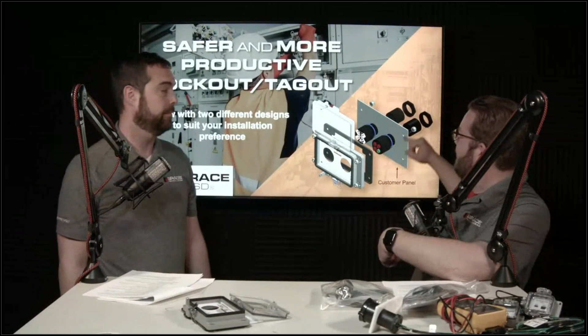You can see it back here - if you have an existing voltage indicator, you just mount the same thing, it goes right around it, and extends that platform out. A lot of OEMs include our R3W voltage indicator, so if you buy an OEM piece of equipment and want to add the ability to test for absence of voltage, this is an option. Likewise, if you just want to remove the R3W voltage indicator, the new check volt fits in the same size hole, so you don't have to worry about a whole new enclosure if space is an issue - you can just swap the product out and add that ability to test for absence of voltage.